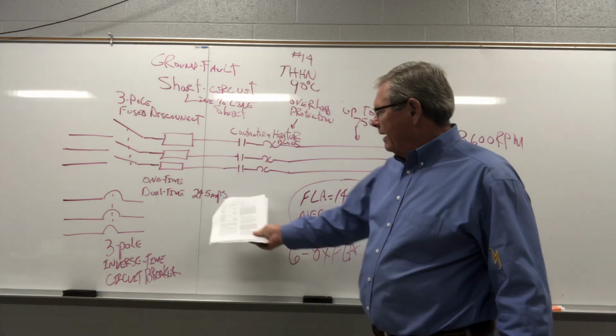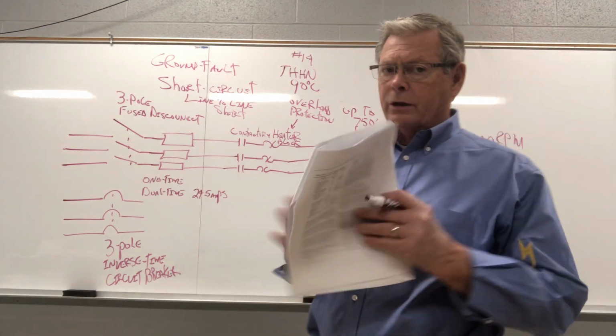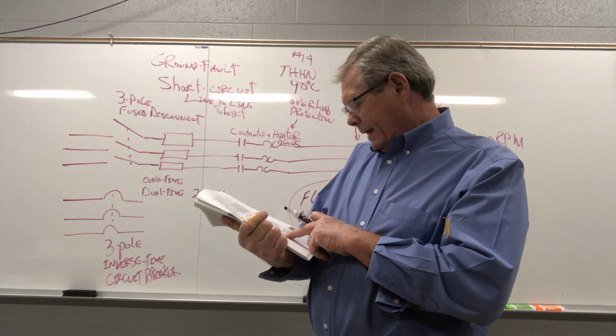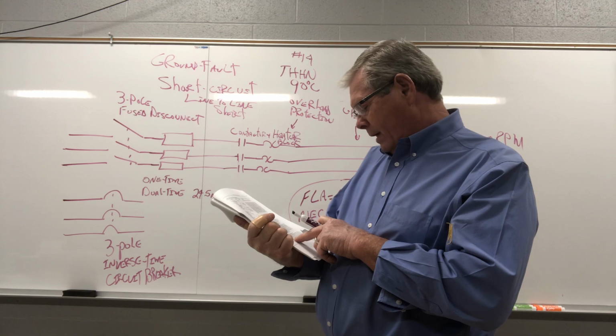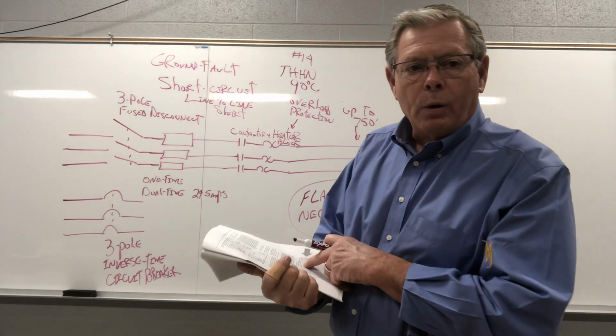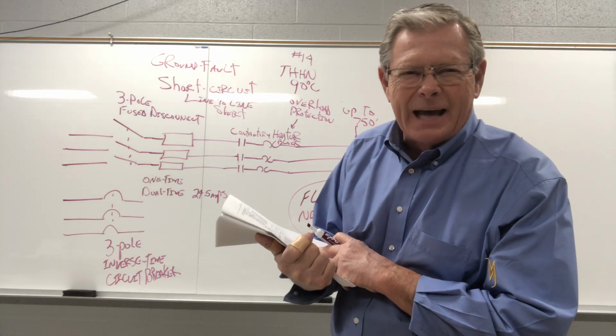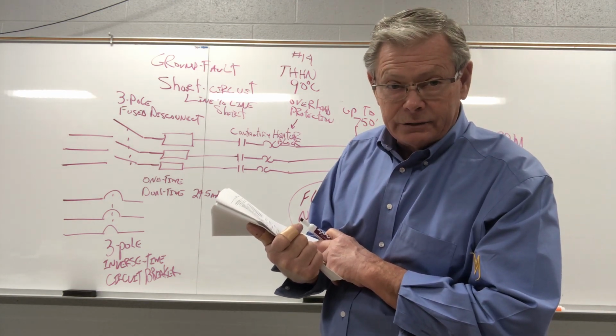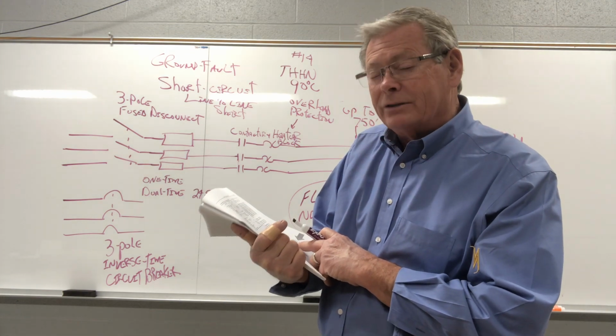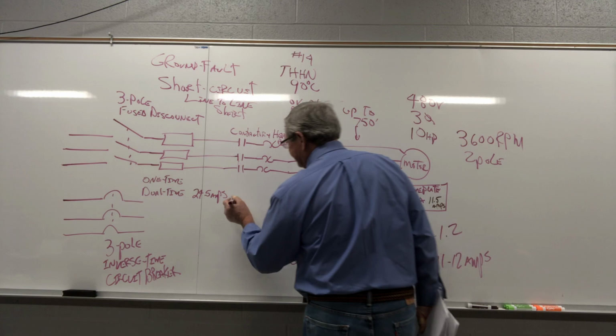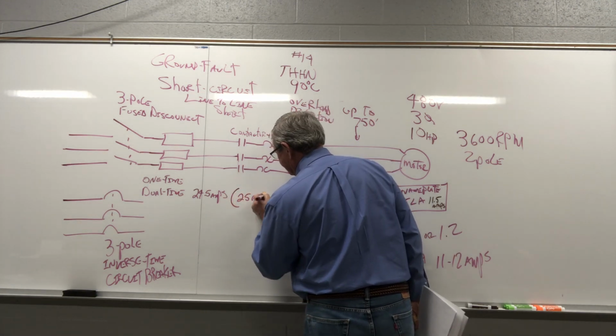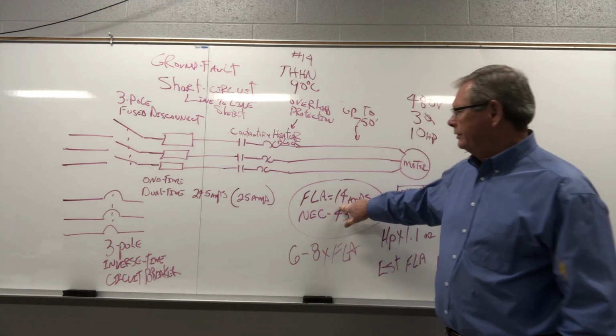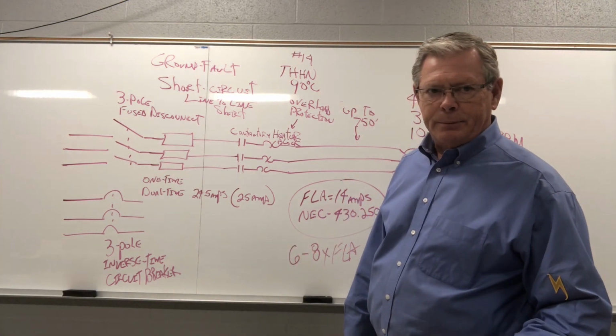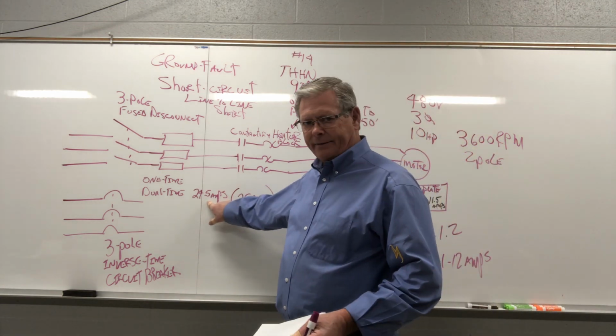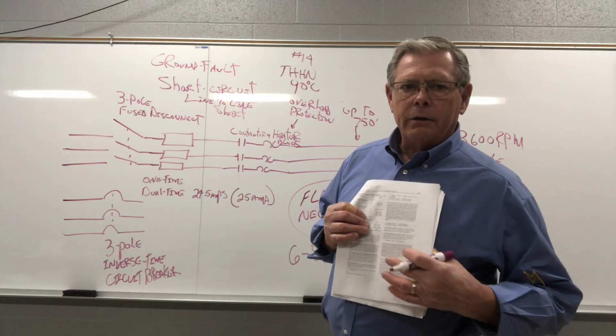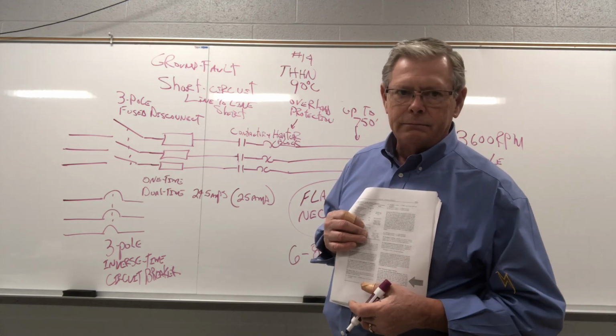So, our calculations took us to 24.5 amps. If we look at 240.6, we've got to find 24.5. They don't make 24.5. But what the code says is you can go to the next standard size higher than your calculation. So the next size up from 24.5 is 25 amp. They make a 25 amp fuse. So we took 14 amps times 175%. They gave us 24.5. Then we look at our chart here. 25 amp fuse is what we need for a dual element, okay?